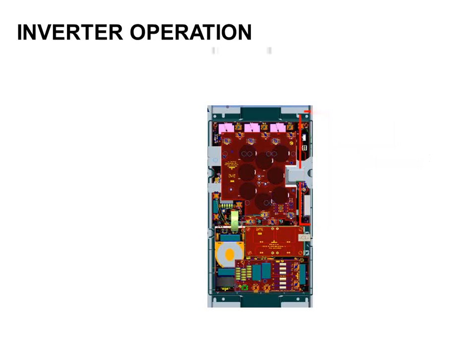It's kind of what the inside of a unit might look like. It looks like a regular unit. It looks like a two-stage unit. There's not really anything abnormal or different there. I still got the reversing valve. I still got the accumulator. The only thing different is that inverter hanging on the outside.